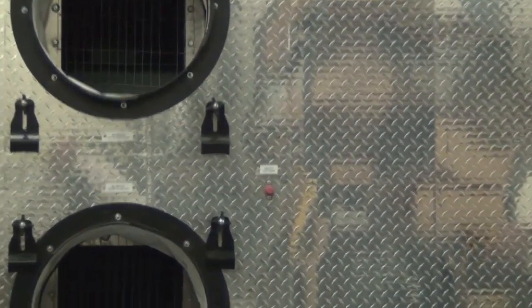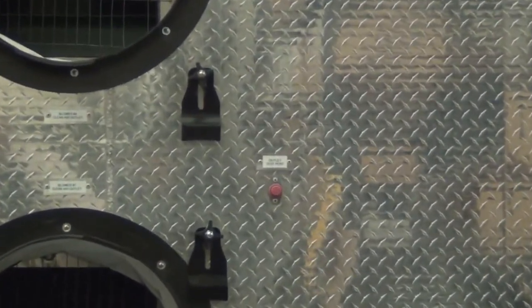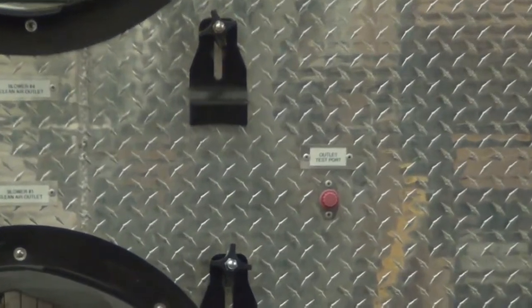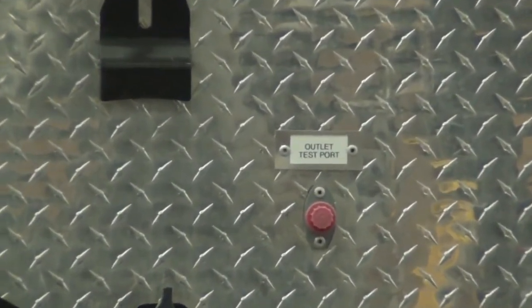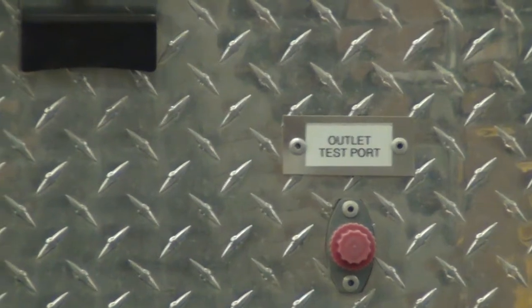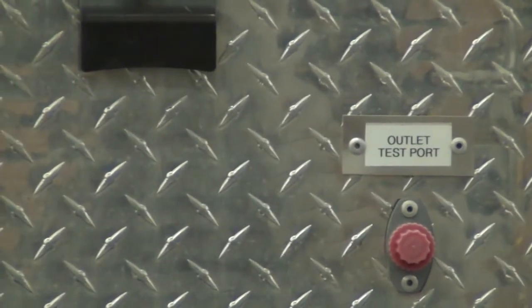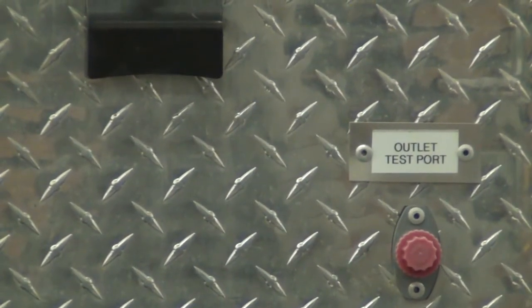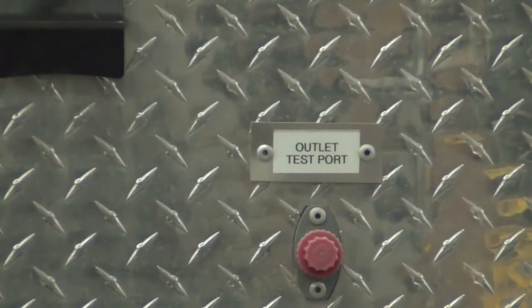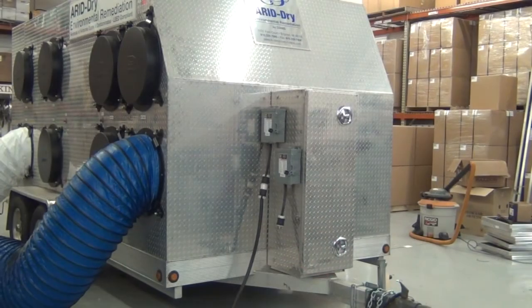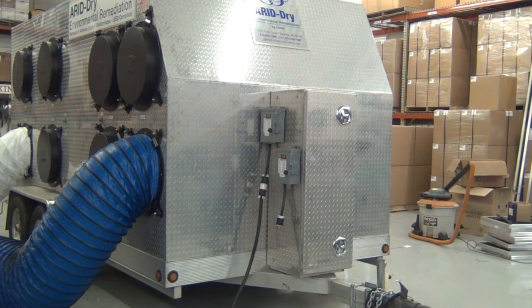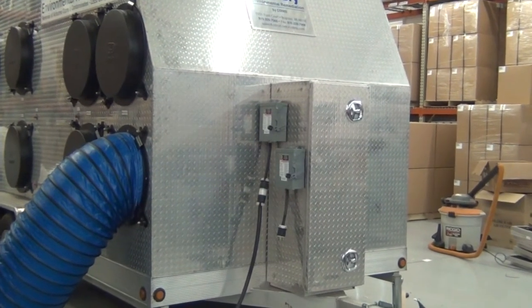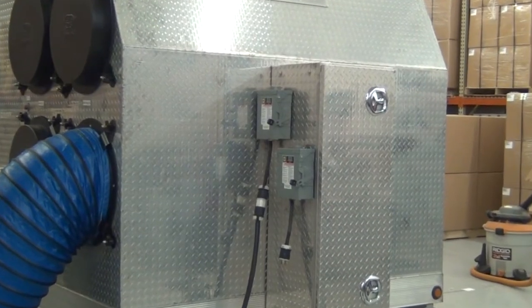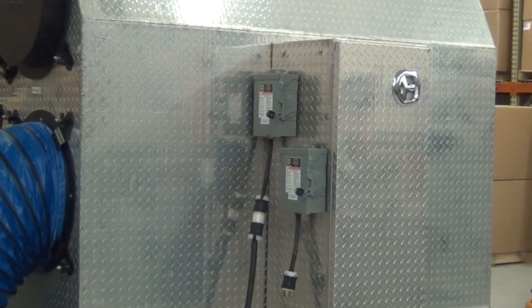These taps can be accessed by simply removing the red protective cover, and then a probe can be inserted in the opening to test for particulate or for pressure drop or flow. The unit is powered by 2 30-amp line cords. They are connected by twist lock fittings to the exterior mounted disconnect switches.